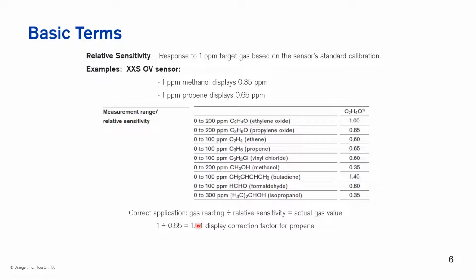One of the other things we talk about with some of the DrägerSensors is relative sensitivity. We have a number of sensors, our organic vapor sensors, our phosphine sensor, amine sensor, even our chlorine sensor that are characterized for multiple gases. So in this example, I'm using our OV sensor that if it's set up and calibrated to ethylene oxide, it has a relative sensitivity of 1. If we're detecting one of these other gases, say propene, it has a 0.65 relative sensitivity. So meaning if I'm using a sensor that's calibrated to ethylene oxide and I'm detecting propene, I'm only going to get 65% of my actual value.